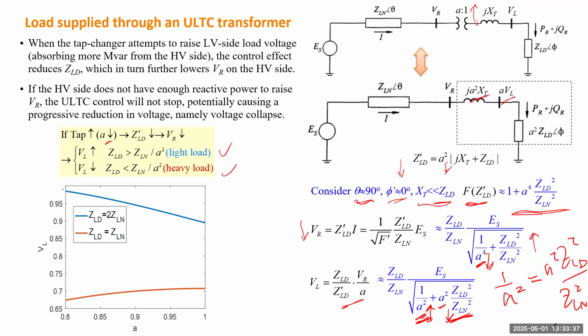So if we just give you some idea, we try two conditions. The first condition is the load impedance is twice the line impedance. This represents a light load condition, so the load impedance is far from the line impedance. The second is when it is just equal to the line impedance. For the first one, you see when the tap moves up, the A decreases, so we are going to move from right to left. The load voltage is growing, so this control is successful. But when the load impedance becomes equal to the line impedance, the voltage is actually declining. So control will fail.